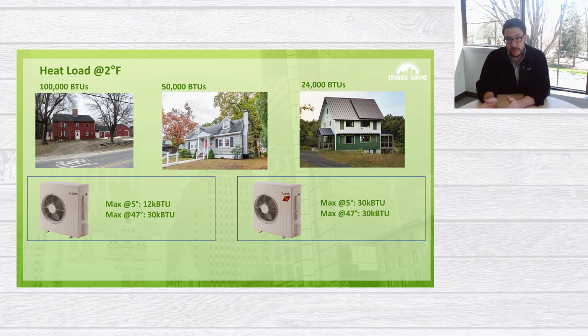If I think about the house in the middle, which requires 50,000 BTUs per hour, and I was putting traditional heat pumps into that home, I'd need 4, possibly 5 heat pumps to meet 100% of that building's heat load. That's because at 5 degrees, that heat pump only provides 12,000 BTUs, while the home needs 50,000 BTUs, so it would be coming up short.